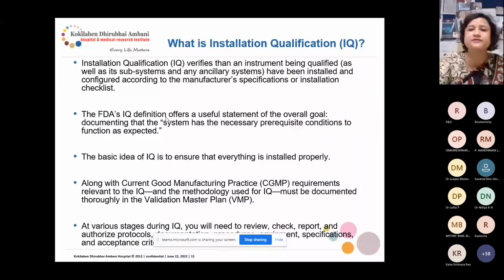IQ verifies that the instrument being qualified, as well as its subsystems and any ancillary systems, have been installed and configured according to the manufacturer's specification or installation checklist. FDA's IQ definition offers a useful statement of the overall goal: documenting that the system has the necessary prerequisite conditions to function as expected. The basic idea of IQ is to ensure that everything is installed properly. Along with the current good manufacturing practice requirements relevant to IQ, the methodology used for IQ must be documented thoroughly in the validation master plan.